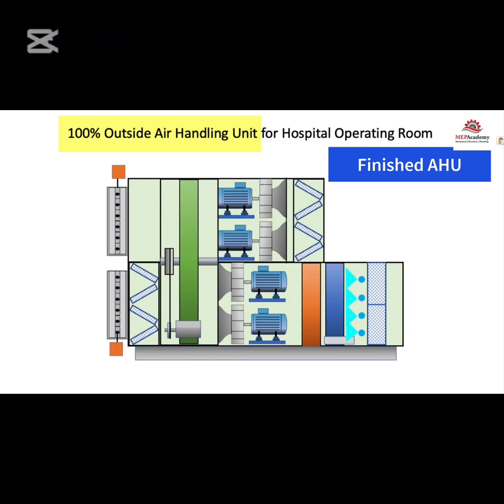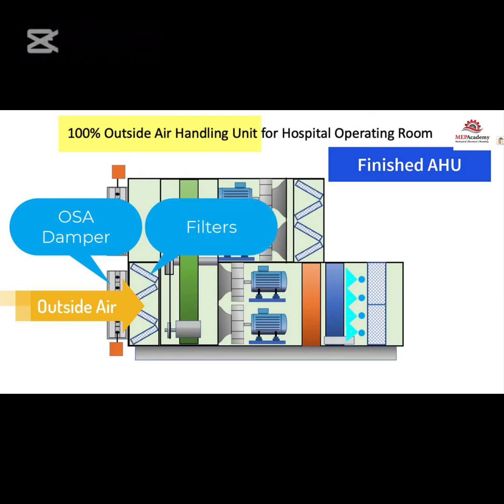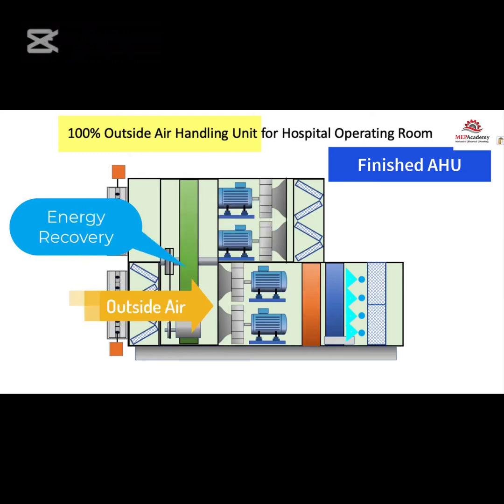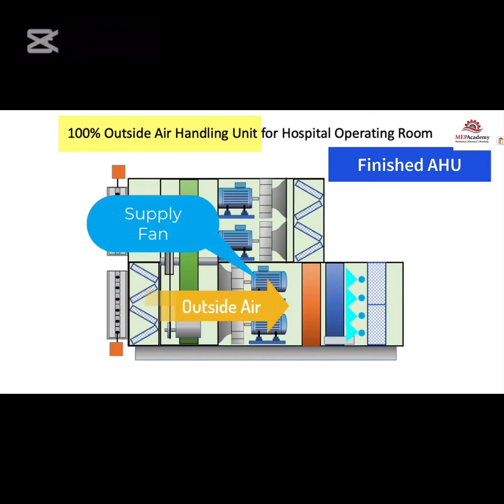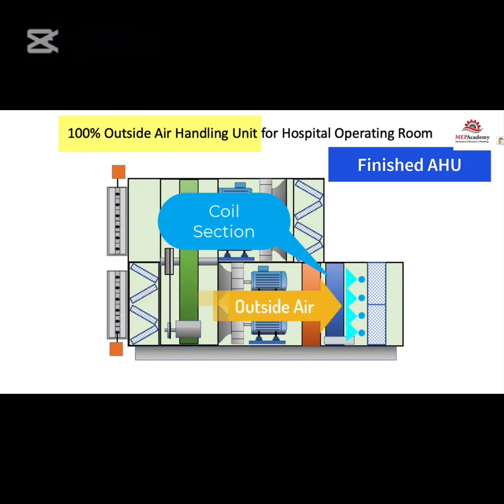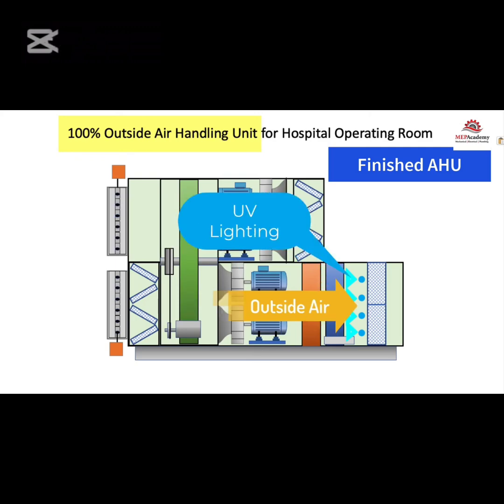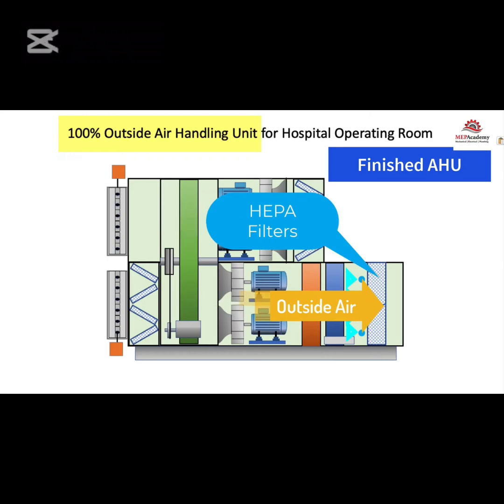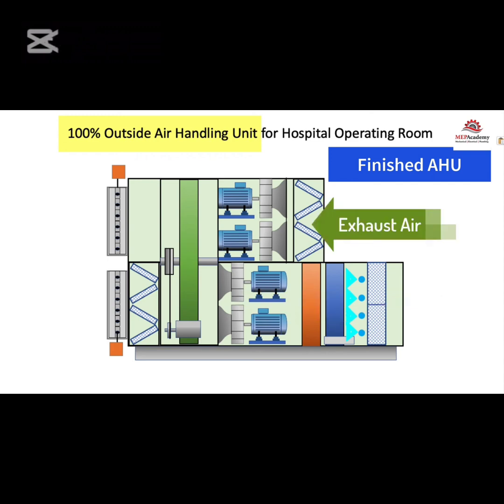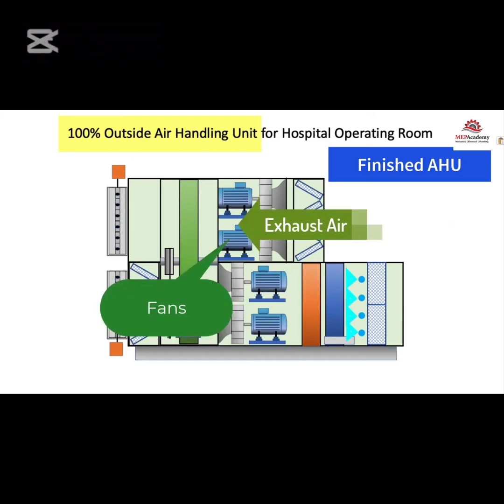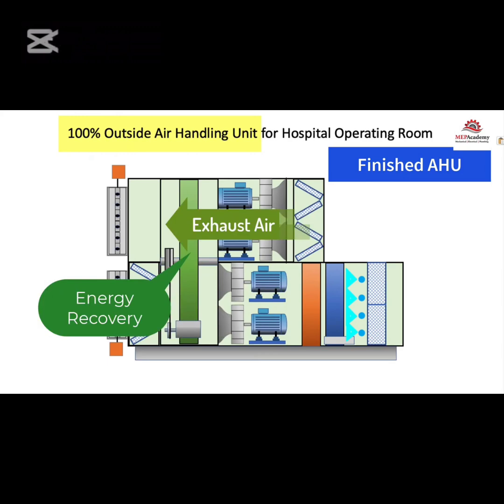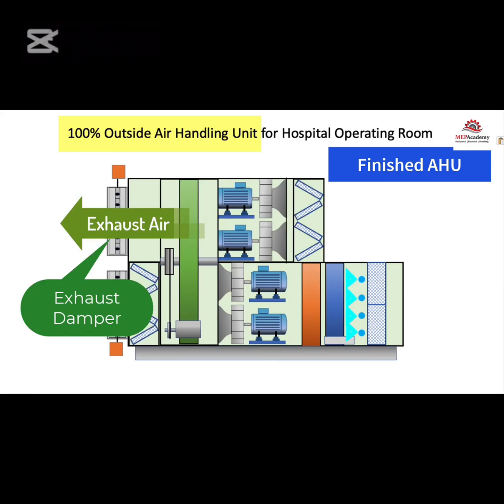So as you can see, our air will enter the outside air damper, go through the pre-filters, and then through the energy recovery wheel where it will recover energy, through the fan, into the coils, and then the UV lighting system will kill the germs, and then it will go through the final filters, the HEPA filters, before it enters the operating room. Coming back from the operating room, we'll exhaust the air through the filters, through the fans, and then capture some of that energy in the energy recovery wheel, and then through and out the exhaust dampers.